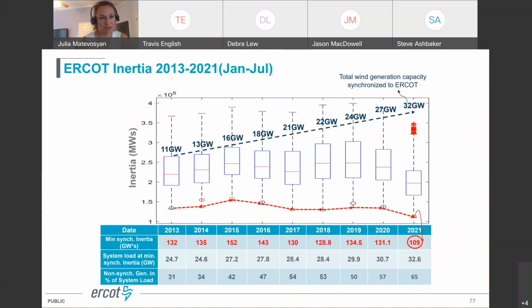I just wanted to say a few words, because I'm talking about weak grid, and you may ask, with single interconnection, we should also be concerned about frequency and inertia and all that. So we started looking at inertia and if it's a concern. Starting from 2013, we set up inertia monitoring, initially offline, and then in 2015 it was added to the control room. So what you're seeing here is each box plot representing the distribution of inertia based on hourly real-time data. And the lowest points basically show you minimum inertia in every year.